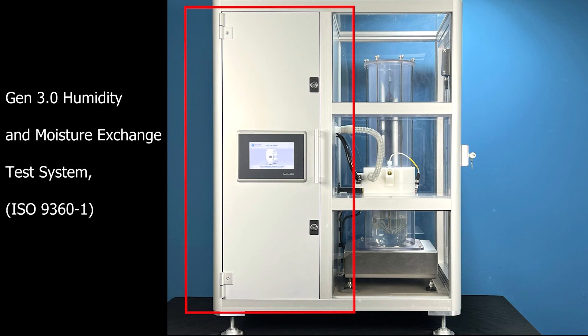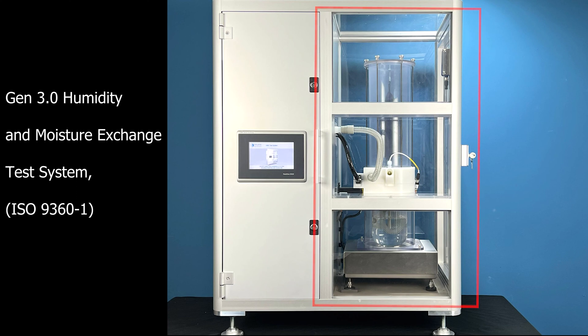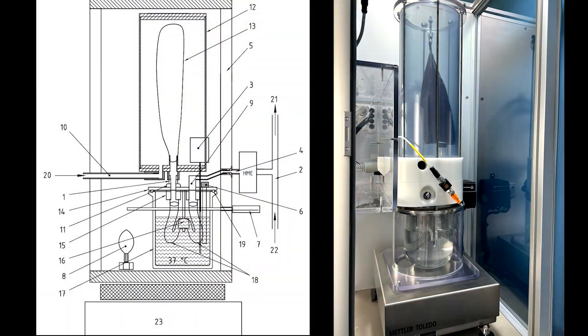There is a window cutout on the left side of the system so the operator can easily verify if the flow generator is cycling. The right half of the system houses the test chamber with quick disconnect connections to the test chamber located at the middle. Inside of the temperature controlled test chamber is the humidity generator which sits atop a high accuracy weight scale.